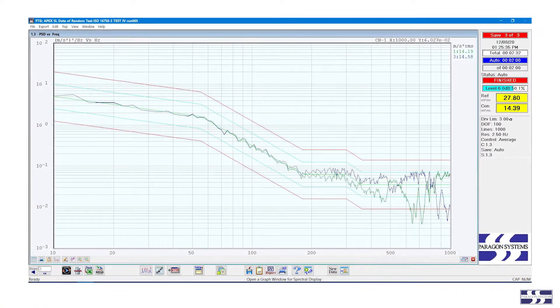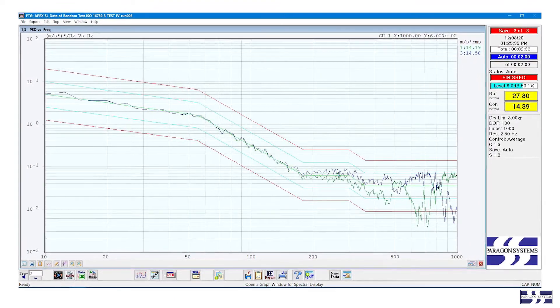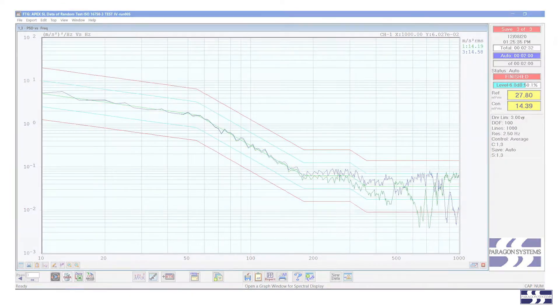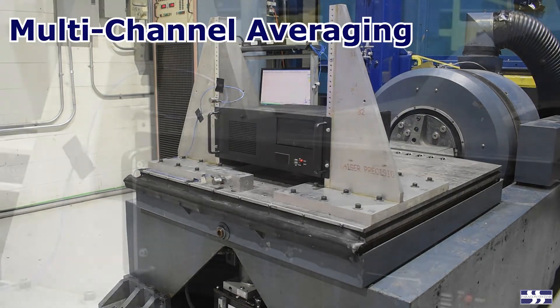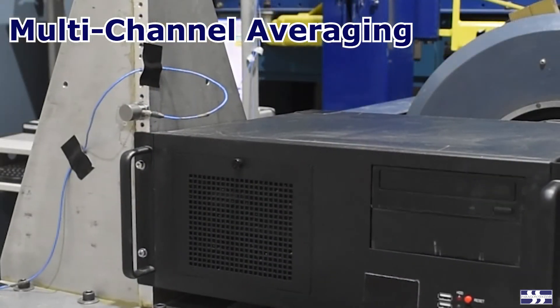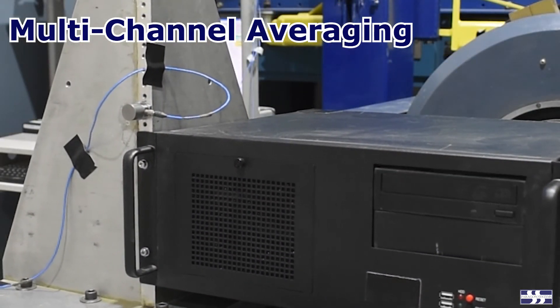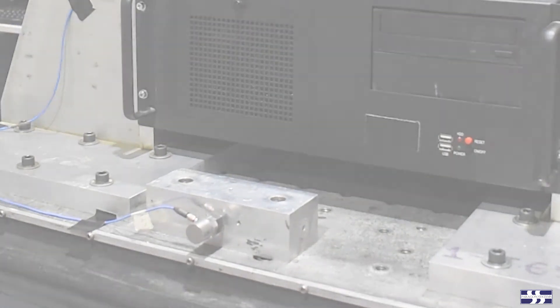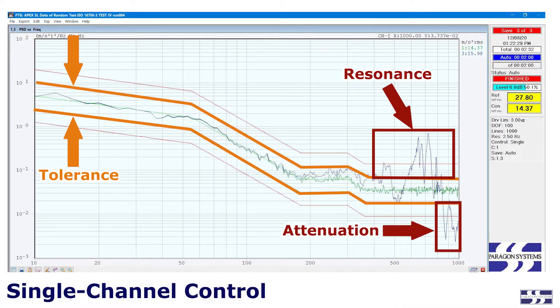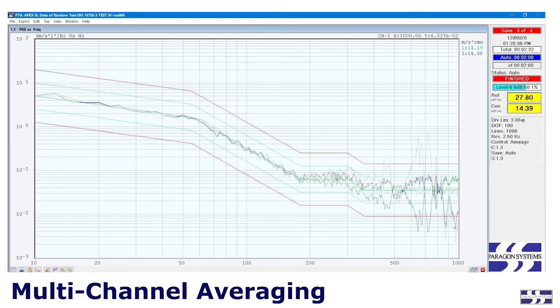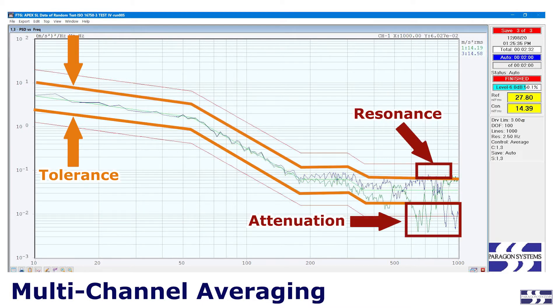Some experimentation with which channels to use in the average calculation may be necessary to get the best possible outcome. This type of control is called multi-channel averaging. In some cases, where the test profile is not excessively out of tolerance at the DUT mounting locations, multi-channel averaging may make it possible to bring all of the acceleration channels within tolerance.